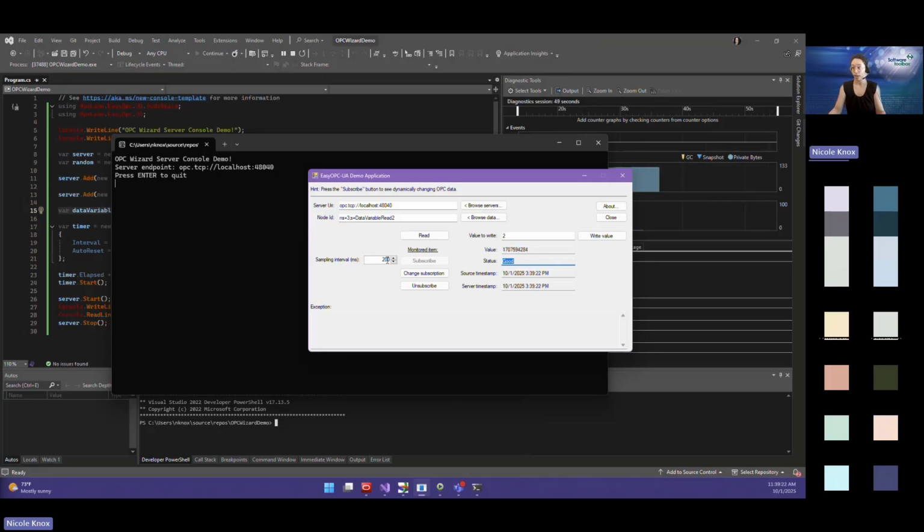This can go the other way, where if the value is changing a lot and you only care about every fourth or fifth value update, simply because that tag just generates a lot of information that you don't necessarily need access to, you can use this to slow down traffic and keep those updates from occurring so quickly, regardless of how quick a client is subscribed to the tag.